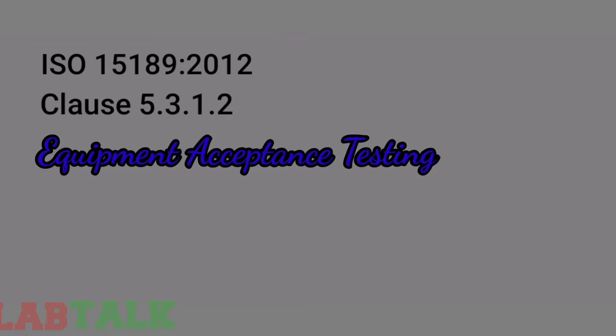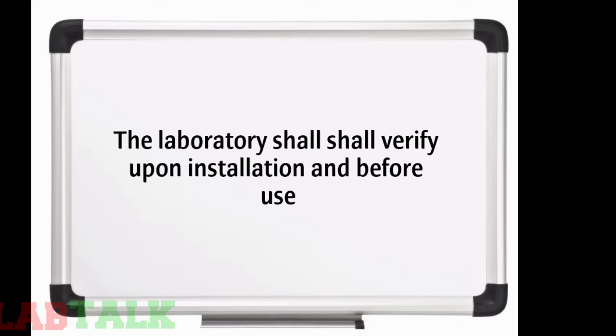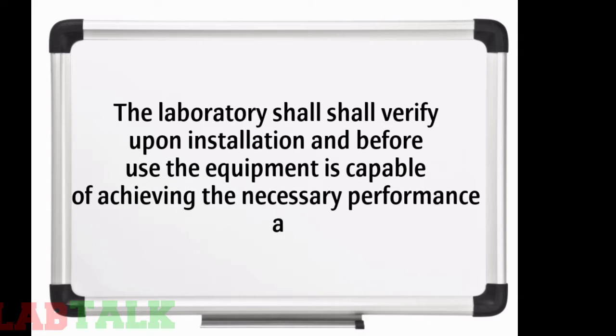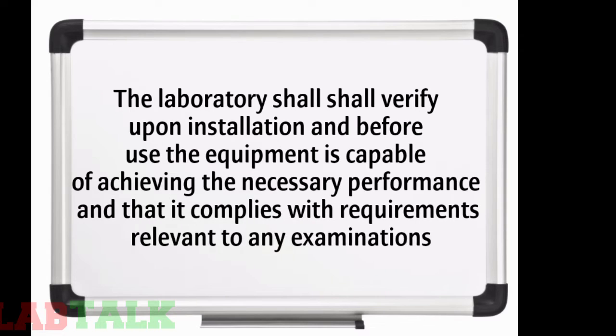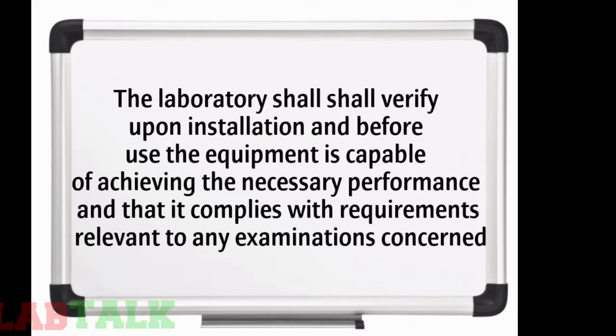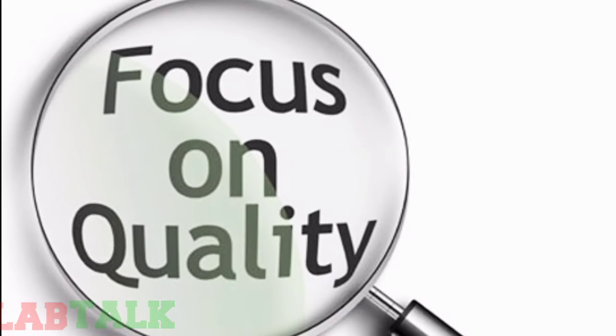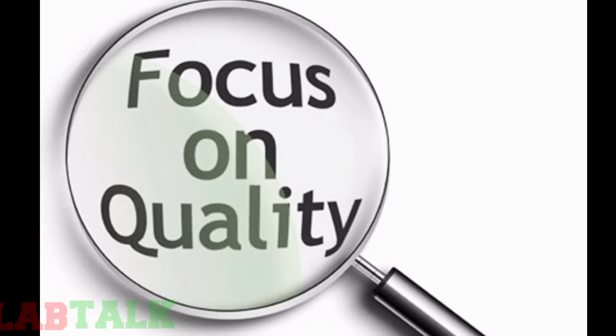ISO 15189:2012, in its clause number 5.3.1.2, that is equipment acceptance testing, mentions the acceptance testing or IQ, OQ, PQ of newly purchased or newly installed instruments. It states that the laboratory shall verify upon installation and before use that the equipment is capable of achieving the necessary performance and that it complies with the requirements relevant to any examination concerned. So at the time of installation of new equipment, the installation qualification, operational qualification and performance qualification should be performed and documented.